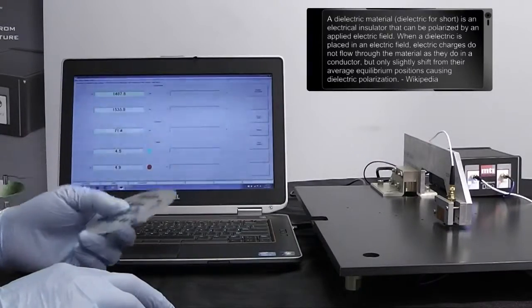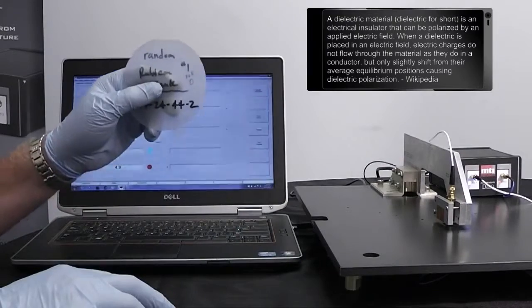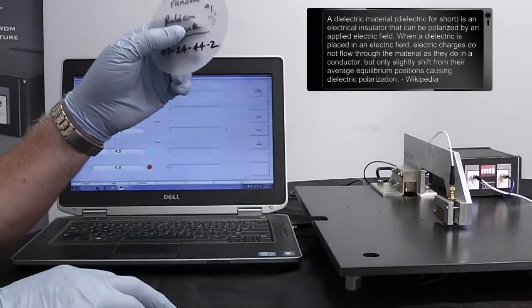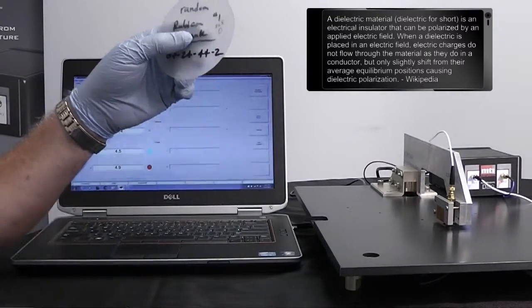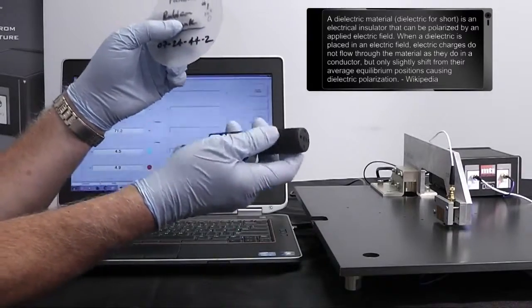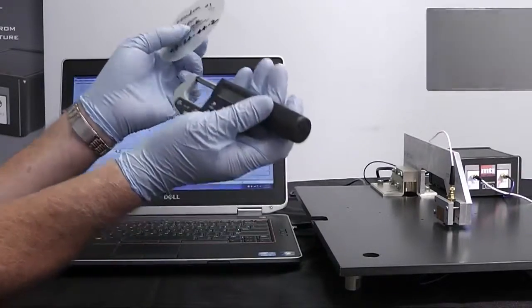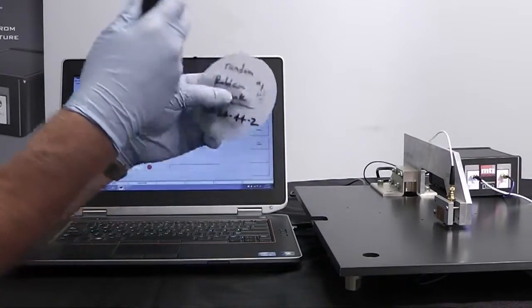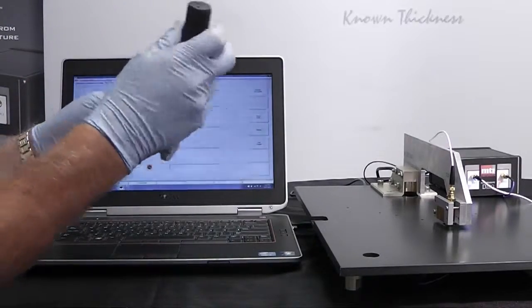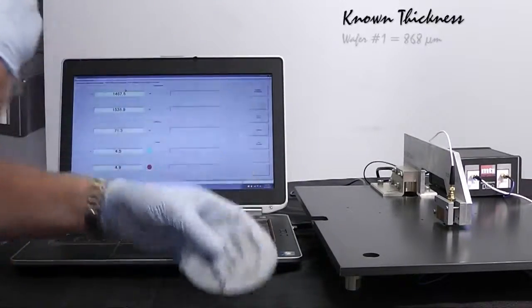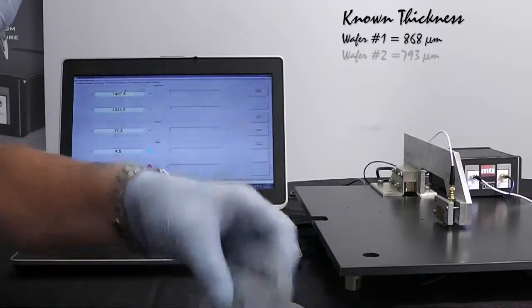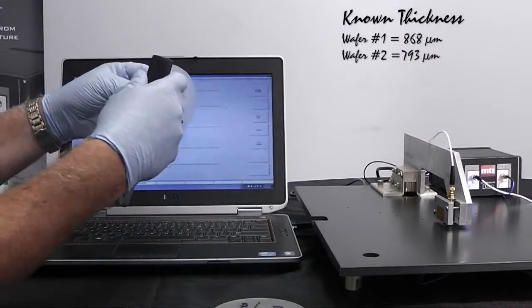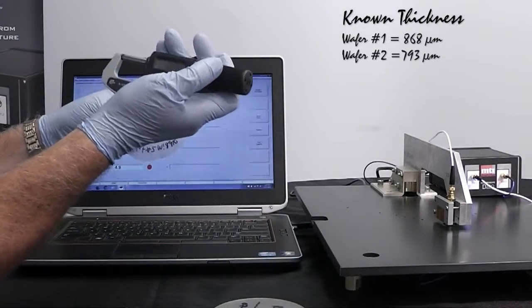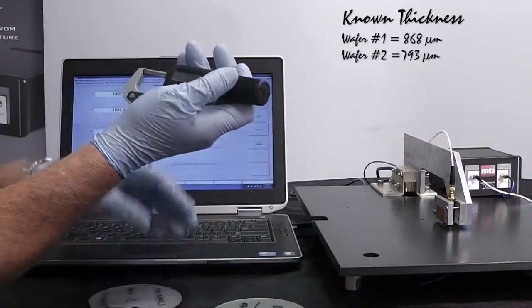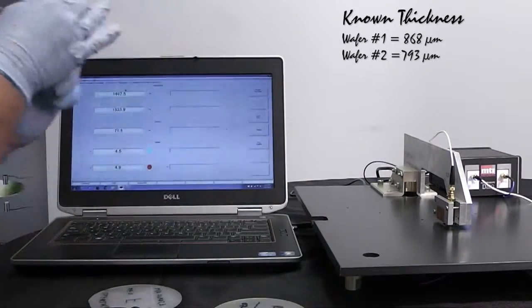Okay, after we get the program started up, what we want to do is to calibrate to 2 known thicknesses on our sapphire wafers here. We have a micrometer here. I've identified 2 areas, one on this wafer right here, where I've mic'd it. I got 868 microns, and I have a second wafer here. This one's 793 microns. And again, we figure that out by using a standard contact micrometer to do that.